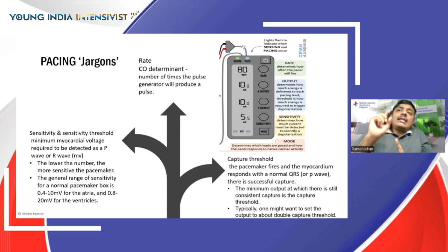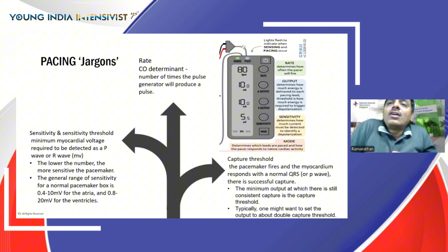The other jargon that we use very often and that needs to be set is the capture threshold. So what does that mean? You know that the pacemaker fires and the myocardium responds with a QRS following that pacing. This is a successful capture, as we call it. The minimum output at which there is a capture is called the capture threshold. This is measured in milliamperes. So you need to understand how we set the capture threshold as well.